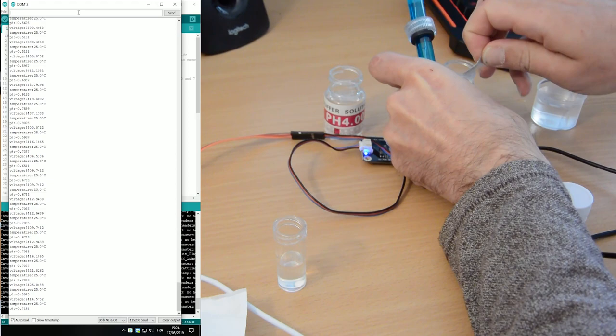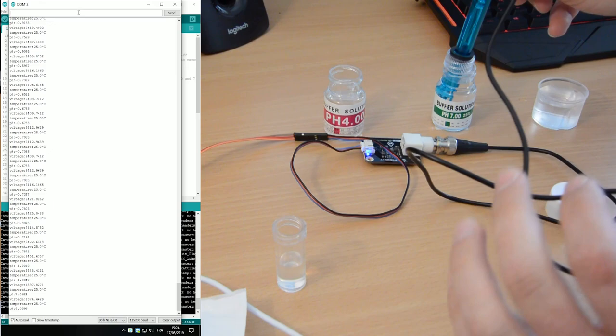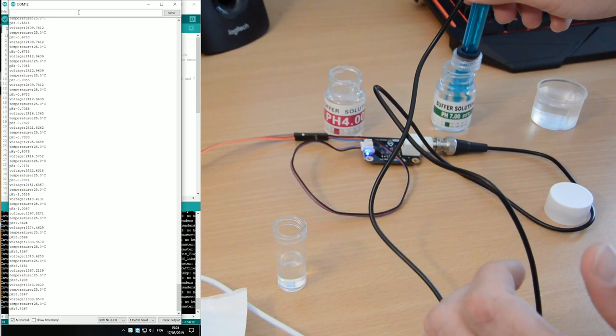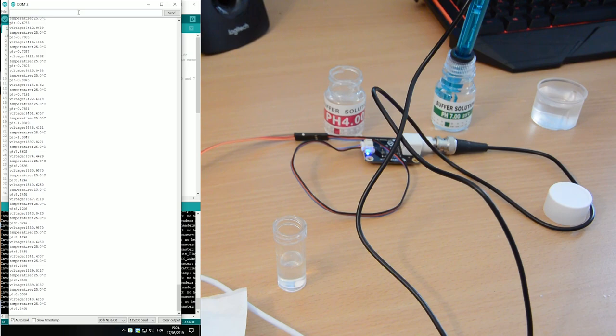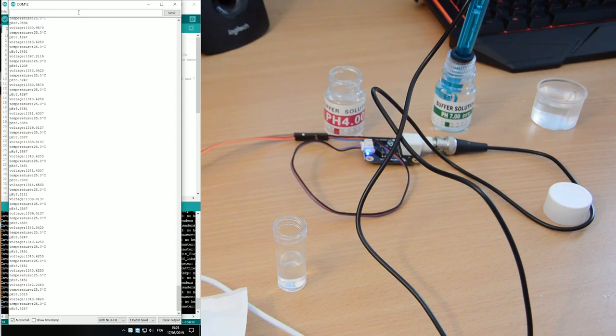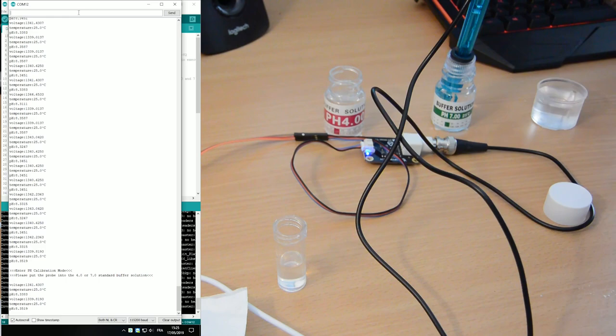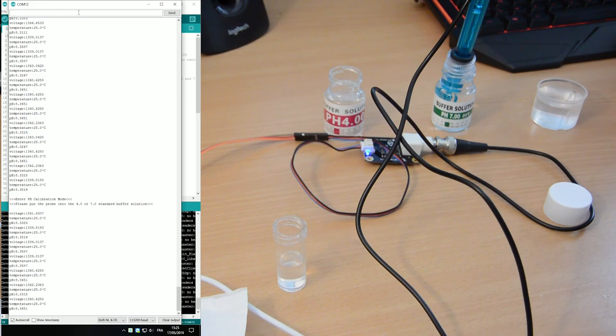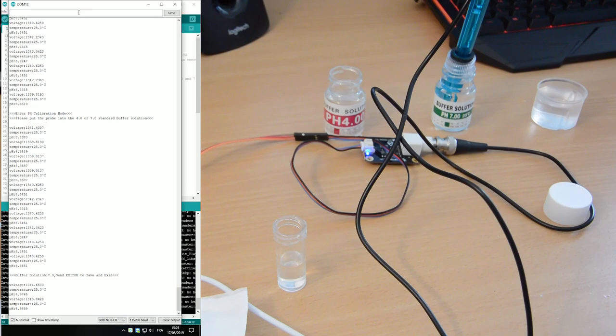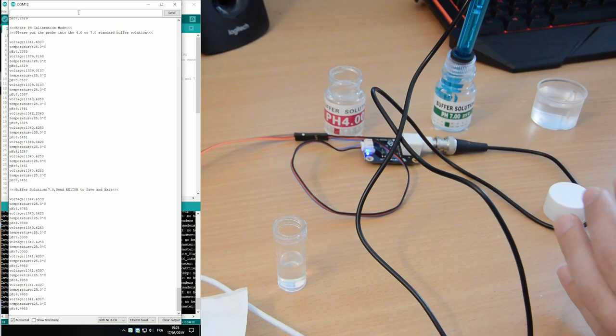Quick reminder for the next video: do that before you record the video. Okay. Probe is in. Stirring. Now it says 8.35, 8.30, 8.35. It seems to be stable enough. So now we do the same thing. Enter pH. You wait for it to be stable. And you type cal pH.